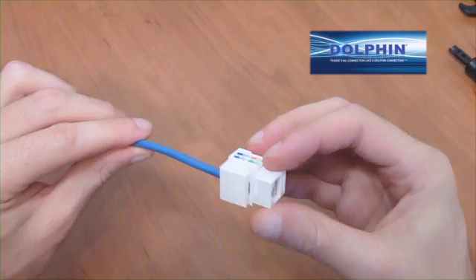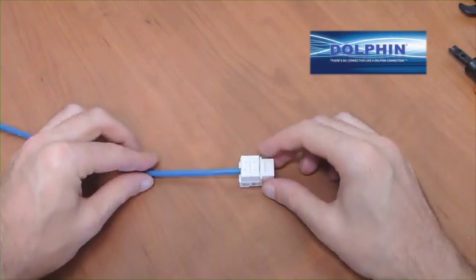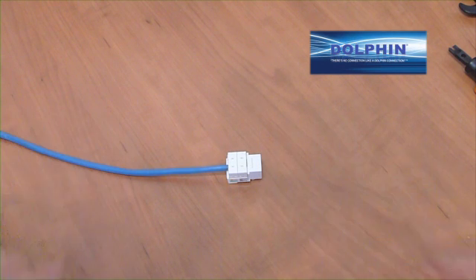Remember, to ensure that you maintain your cable rating, make sure that the outer cable insulation abuts cable entry canal of the jack and do not unnecessarily expose twisted pairs.